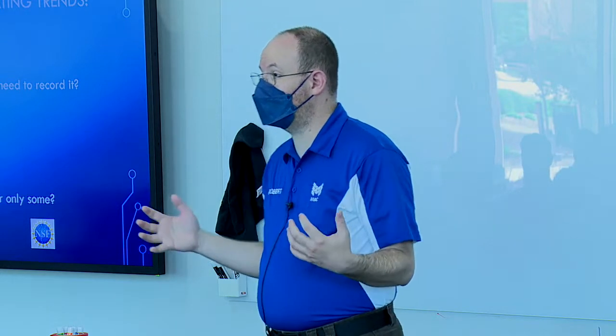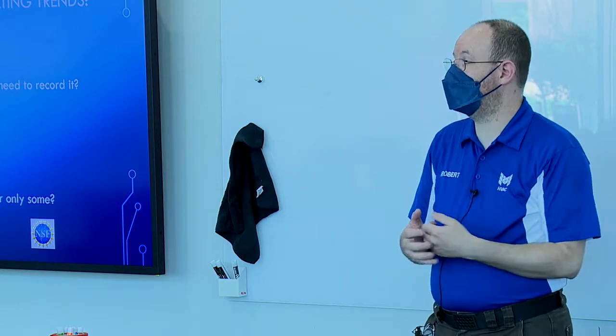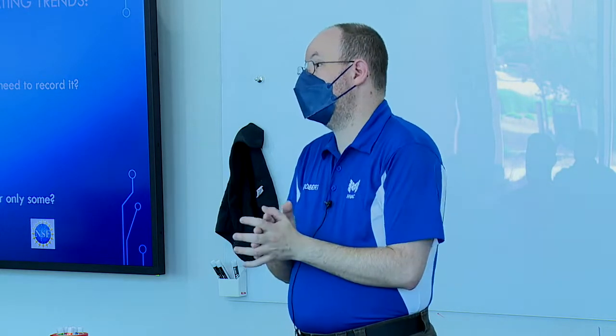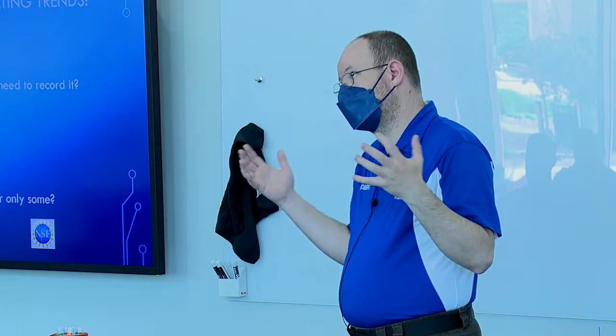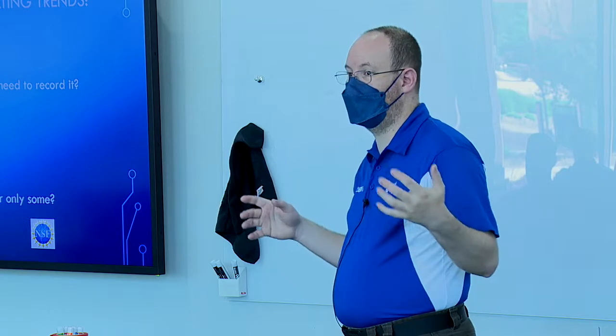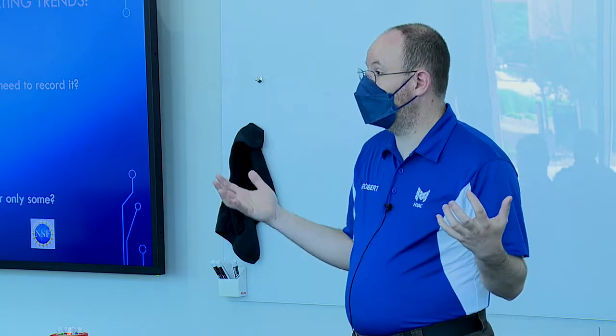That will affect what we want to do with it, how we're going to record it, how much space that data takes up. Things that turn on and off don't take up a lot of data usually for trend logs. Things that are temperatures, analog values, those frequently take much more data space.